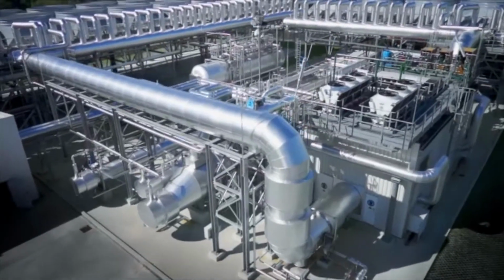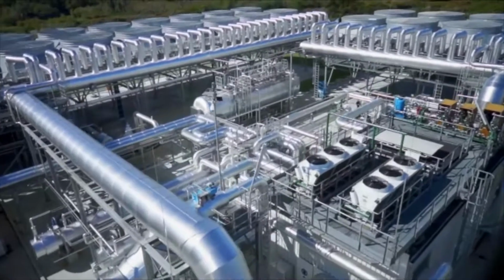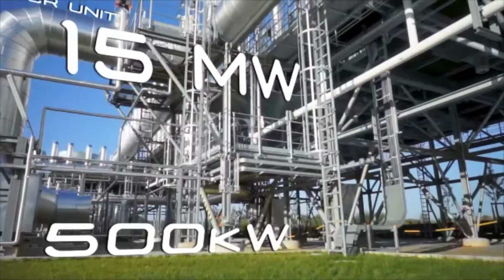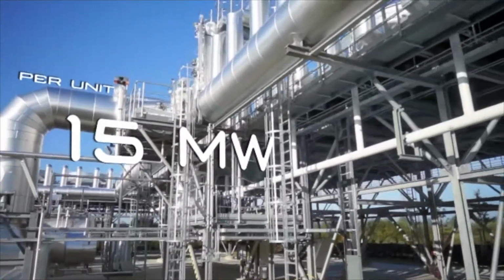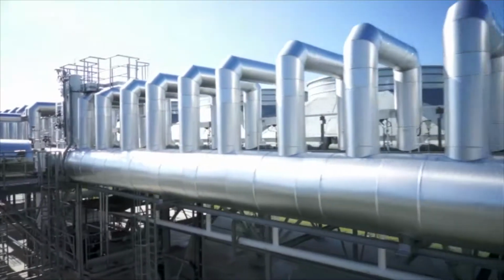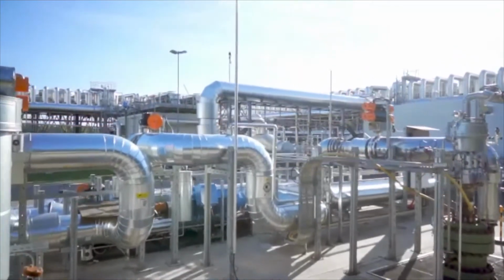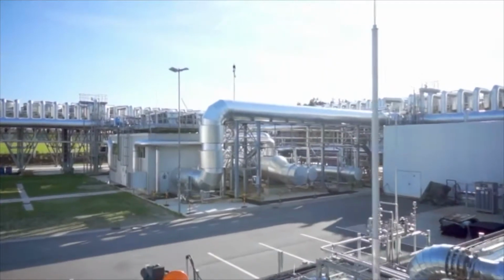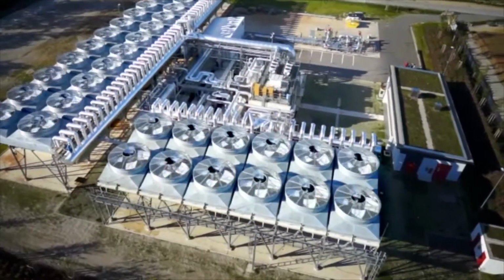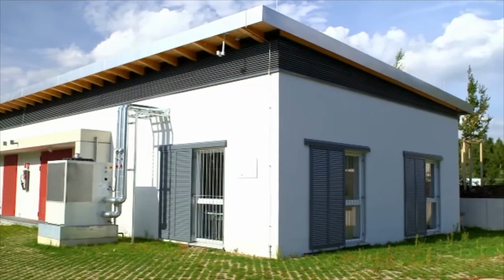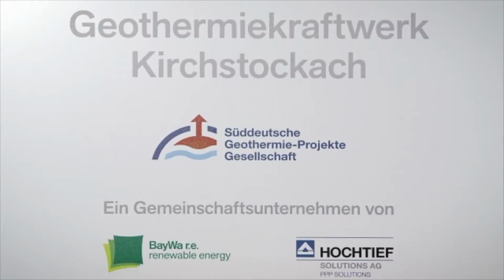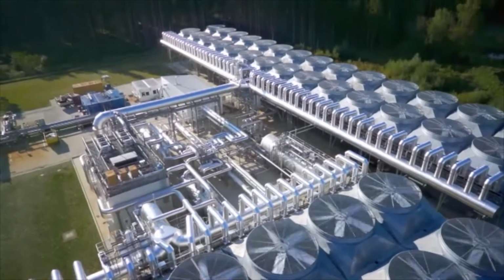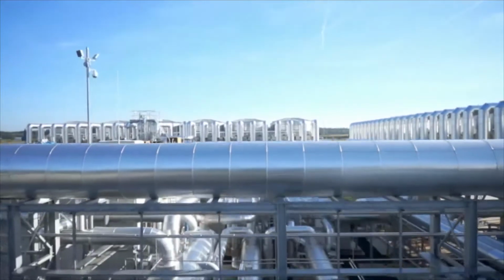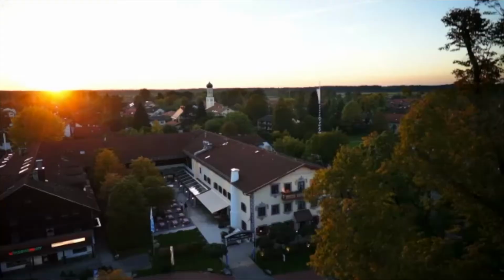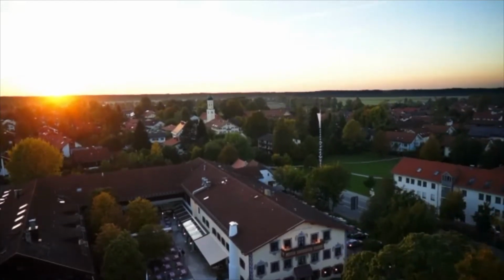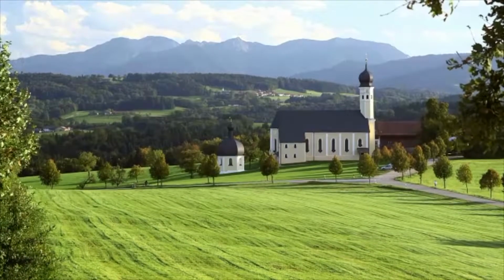Turboden solutions cover every kind of geothermal resources, from low-temperature water to high-enthalpy steam, with modules from 500 kilowatts to 15 megawatts electrical output. The minimum temperature conveniently exploitable is around 100 degrees centigrade. Hochtief Energy Management, a company specialized in energy projects, subsidiary of the construction group Hochtief, has developed with Turboden 2 geothermal power plants, 5.6 megawatts each. The 2 plants have been commissioned and started up in 2013 to supply electricity to the Bavarian grid.